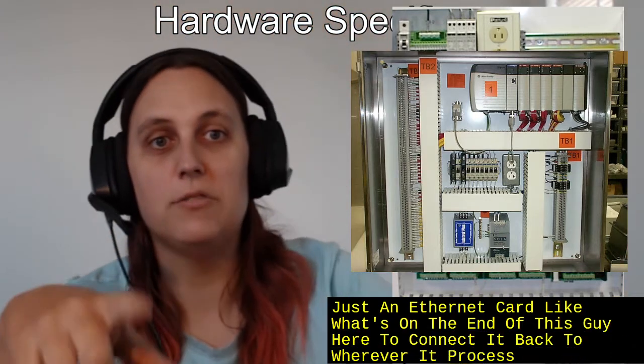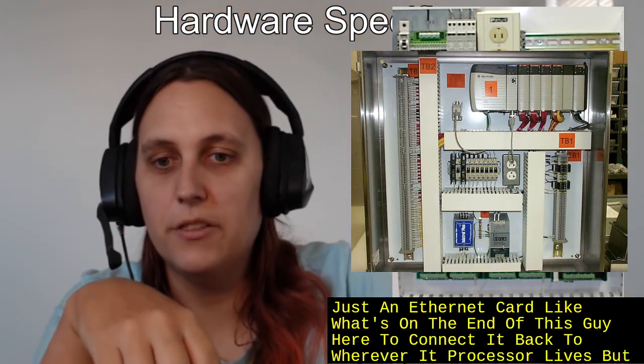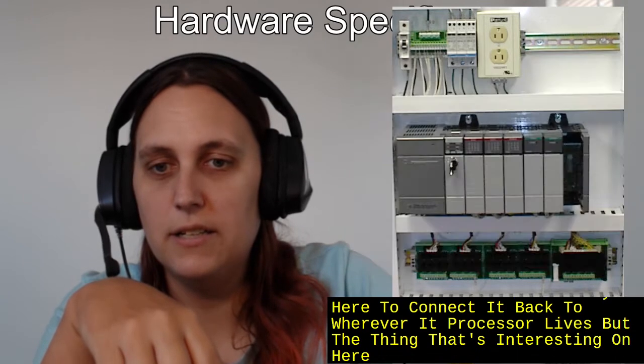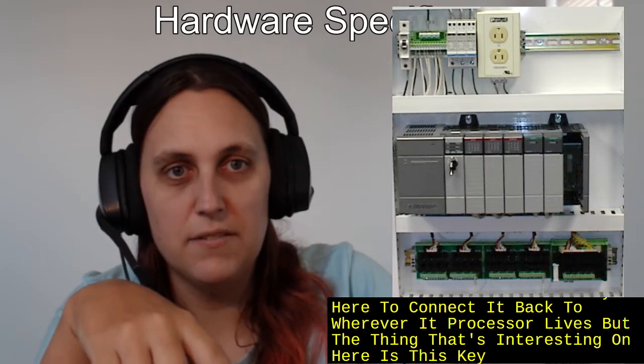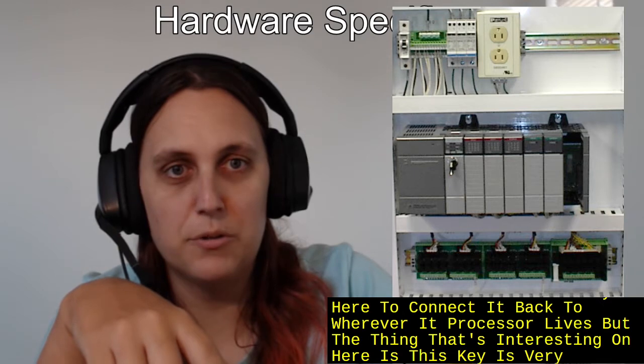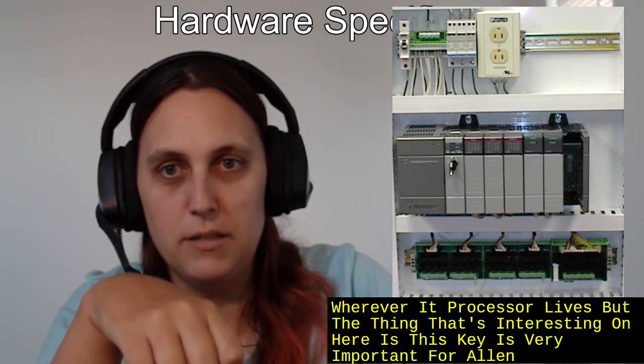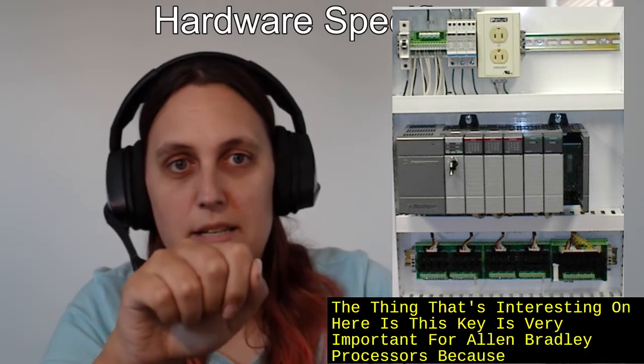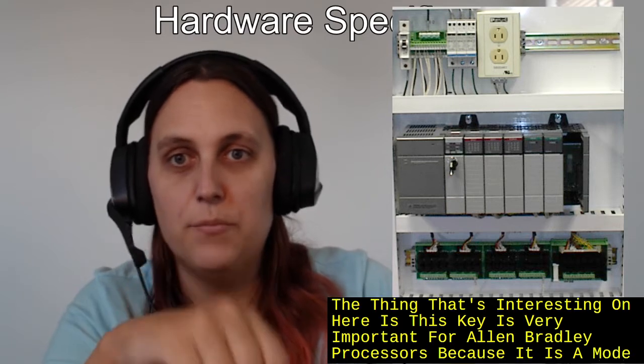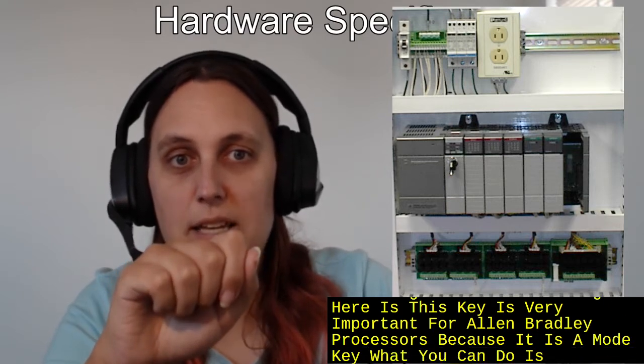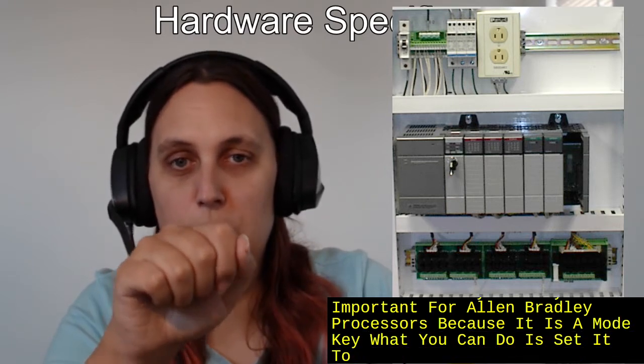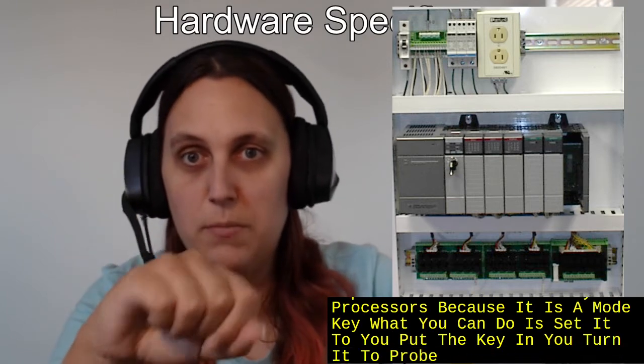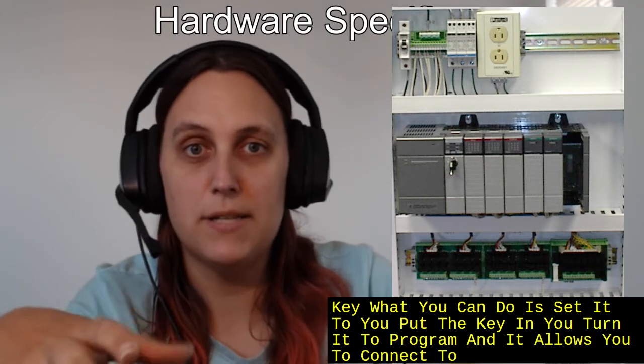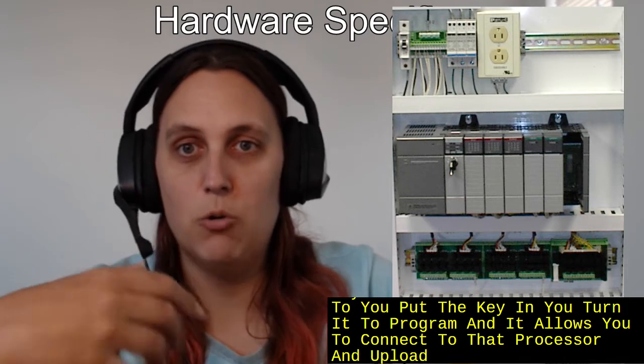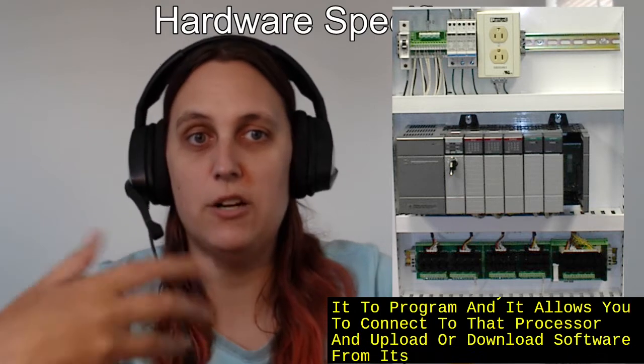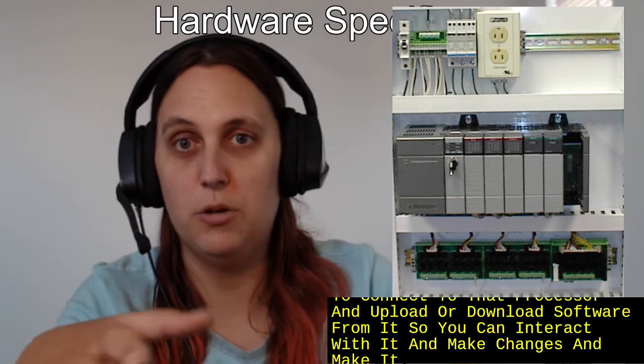But a thing that's interesting on here is this key is very important for Allen Bradley processors because it is a mode key. You put the key in, you turn it to program, and it allows you to connect to that processor and upload or download software from it so you could interact with it and make changes and make it do what you want it to do.